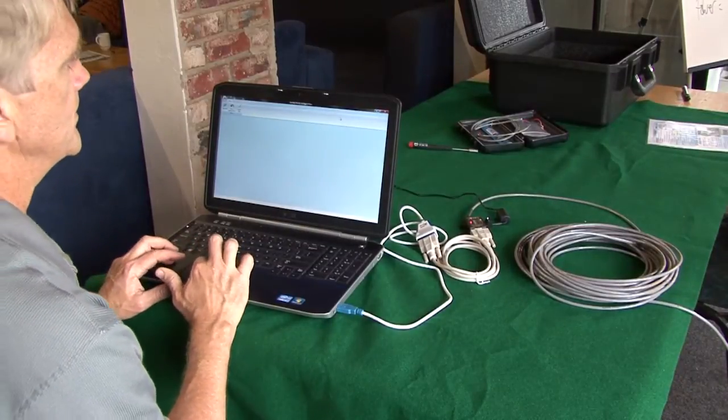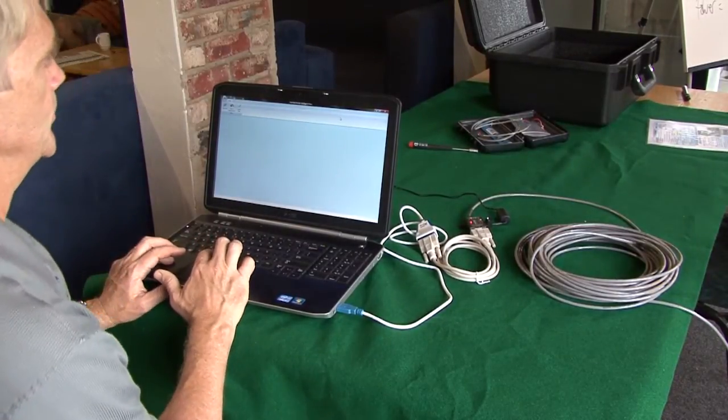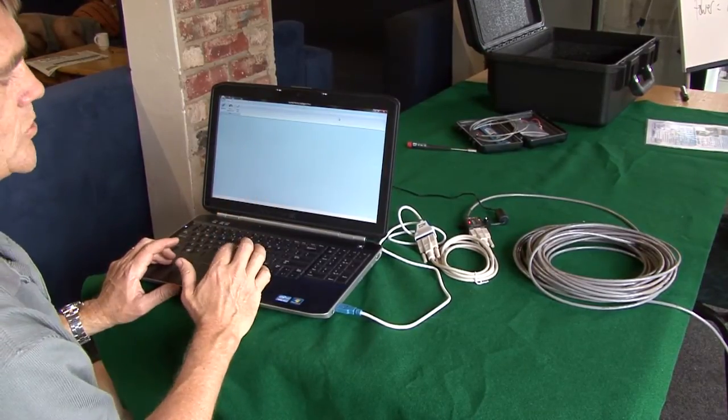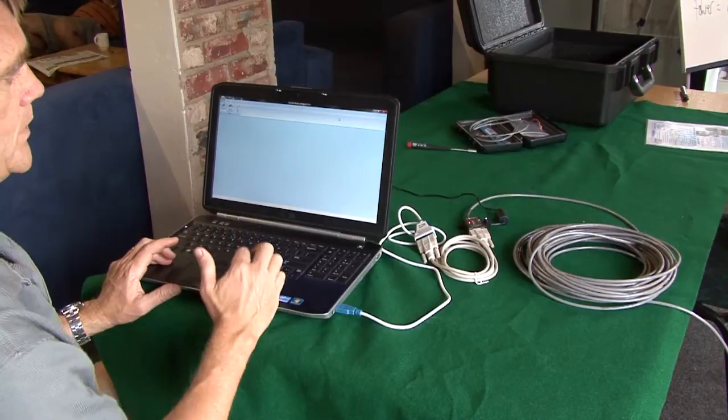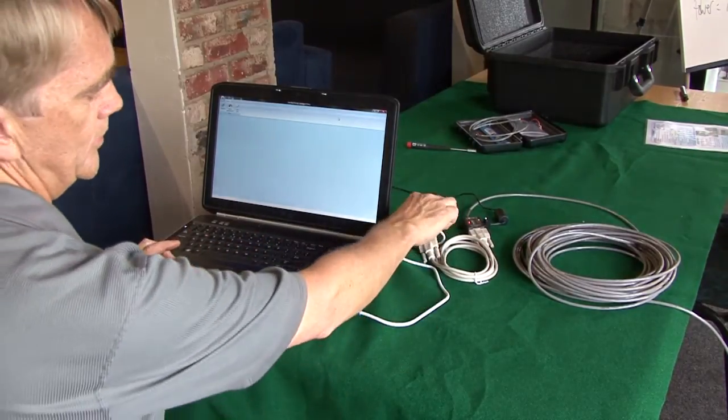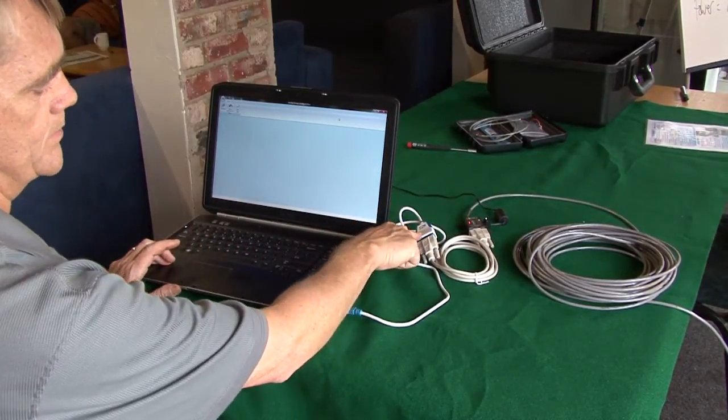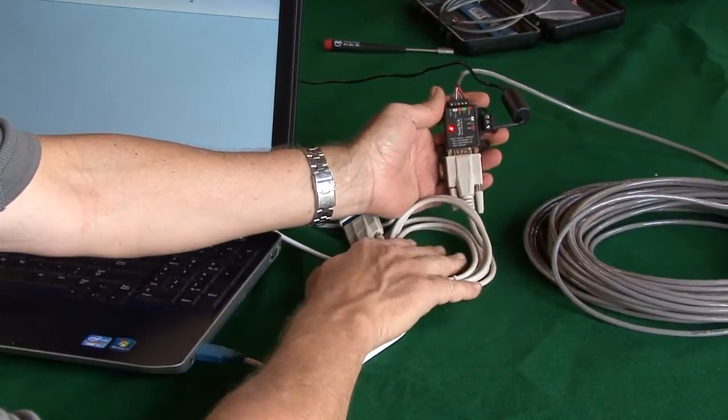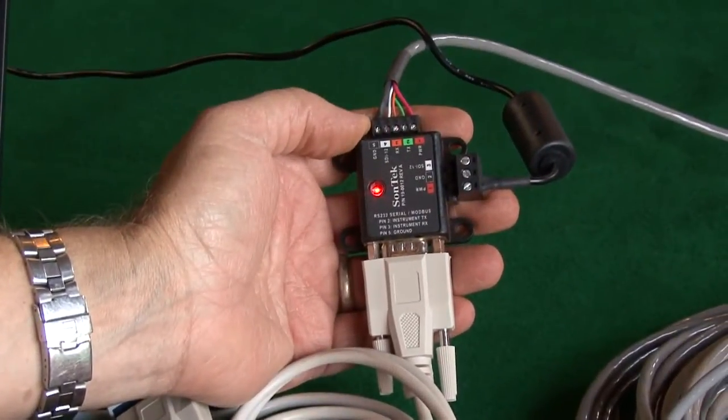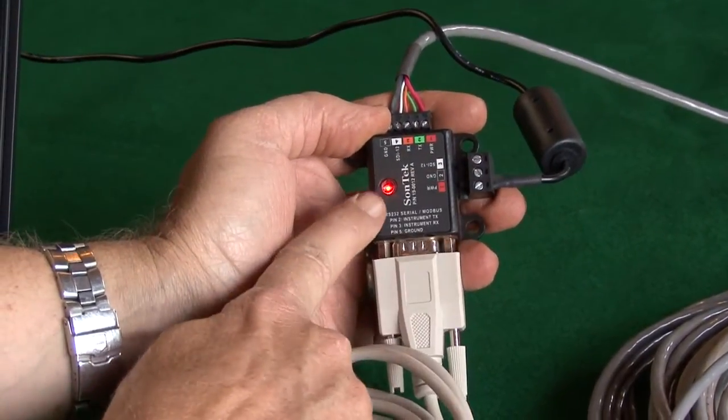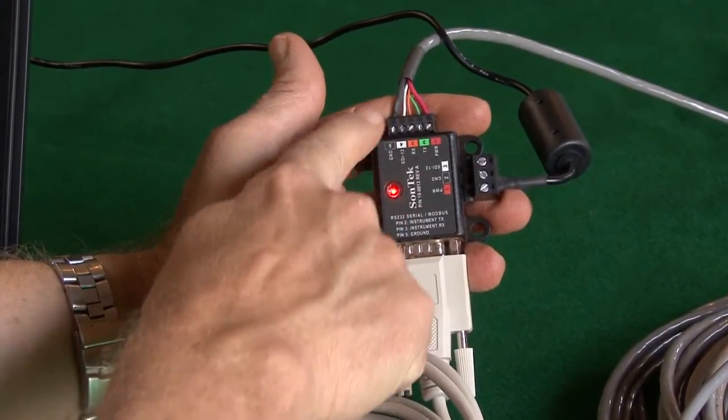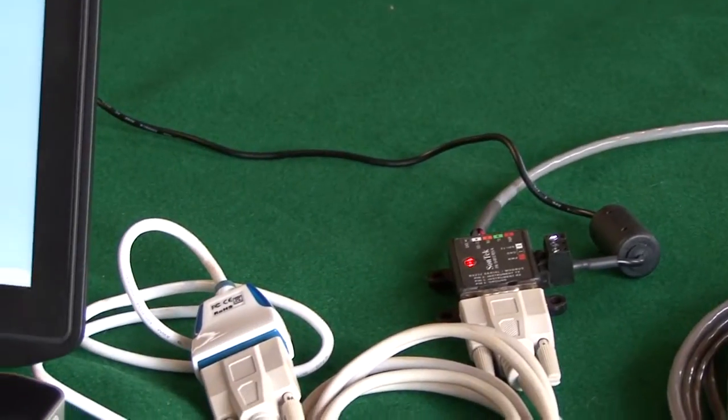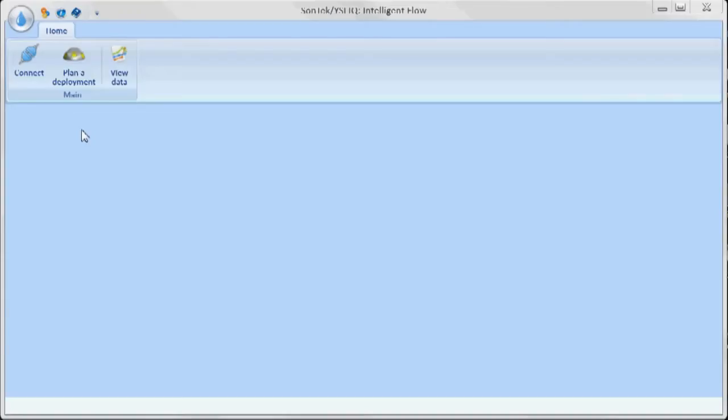What I want to show you here is just a quick example of how to program the instrument once it's been installed. Just briefly, I have the IQ software that I've installed and opened on my laptop. Here's the USB to 232 converter that's plugged into the RS-232 cable. Here's the power and communications interface. Here's where we're supplying the power. You can see the red light indicates that there's power to the system. And this is the terminal blocks with the cable that goes to the IQ that's installed in the water.